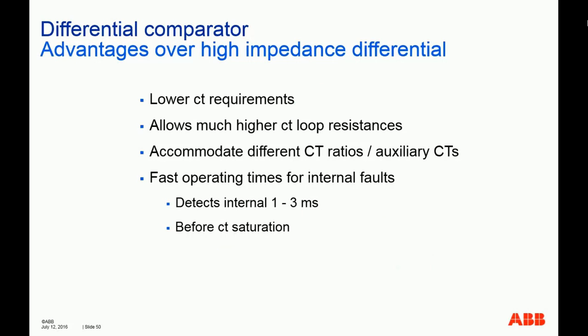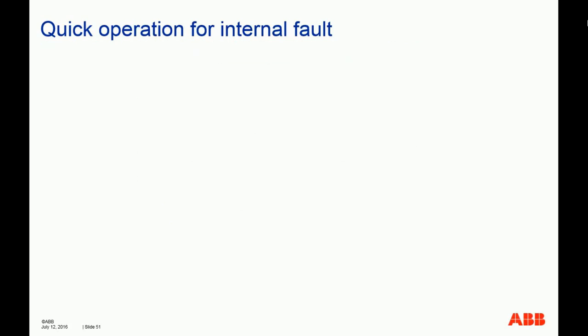So what are the advantages of the modern differential comparator? Obviously, a lower CT requirement. The CTs don't need to match each other anymore. Usually, it can tolerate 10-to-1 ratio differences in the same parallel differential circuit. It can allow much higher CT loop resistances, because the burden of the relay is very low nowadays. It accommodates different CT ratios, no auxiliary CTs are needed right now, and it has fast operating times for internal faults. It will detect an internal fault in 1 to 3 milliseconds as long as you provide a free, unpolluted CT secondary for that amount of time.